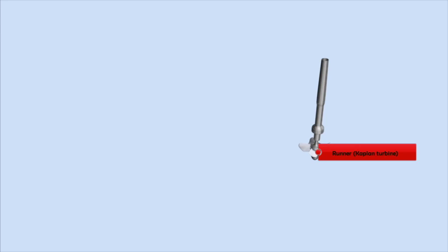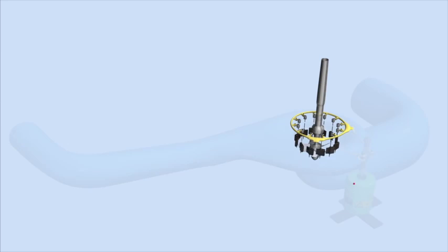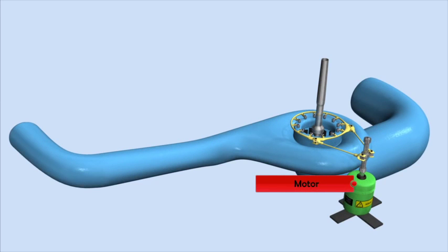The runner of a Kaplan turbine looks like a propeller or the screw of a ship. Adjustable pitch vanes enable it to work efficiently over a range of flow rates. The pitch vanes are driven via an electric motor.